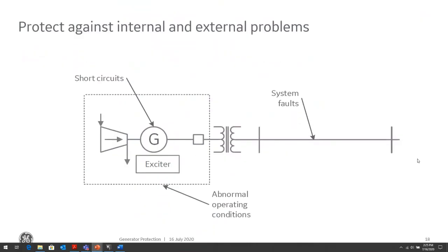So what are we protecting against? We're protecting, obviously, against internal faults within the generator, short circuits within the generator, and we're protecting against internal abnormal operating conditions, as well as faults outside the generator zone, which we refer to as system faults. So the task of the generator protection is to avoid problems from internal short circuits, these abnormal operating conditions that we'll talk about, and from the system faults.